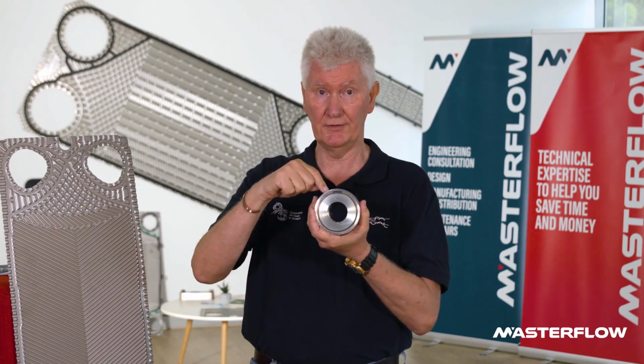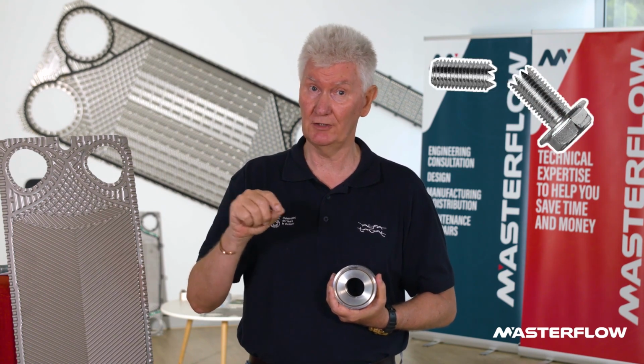Other suppliers go in a different direction. They use relatively small bolts and a lot of them. Typically we might have 6 bolts on our heat exchanger, 4 of them sitting on these bearing boxes. One of our competitors might have 16 bolts of half the diameter, so their maintenance crews spend a lot more time undoing the exchanger. Those bolts are also susceptible to snapping under too much load, because they don't have the same strength. So these are the quiet differences.